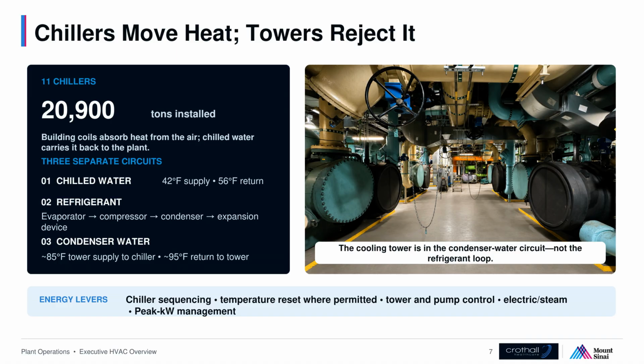The chiller plant does the opposite of the boiler plant. It removes heat from the buildings. The easiest way to understand it is as three separate circuits. First is the chilled water loop. Water leaves the plant at about 42 degrees, absorbs heat at building coils, and returns at about 56 degrees under representative design conditions. Second is the closed refrigerant circuit inside the chiller. Refrigerant absorbs heat in the evaporator. The compressor raises its pressure and temperature. The condenser transfers that heat into condenser water, and the expansion device drops the refrigerant pressure so the cycle can repeat.